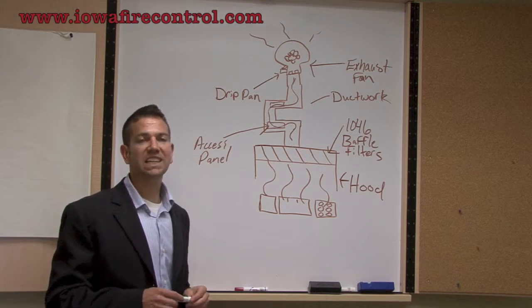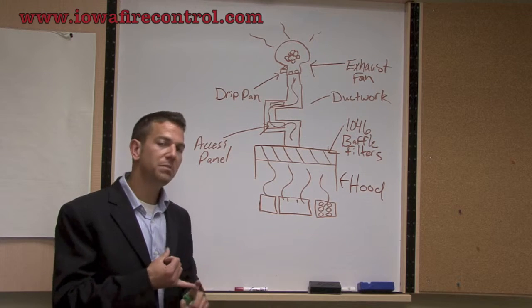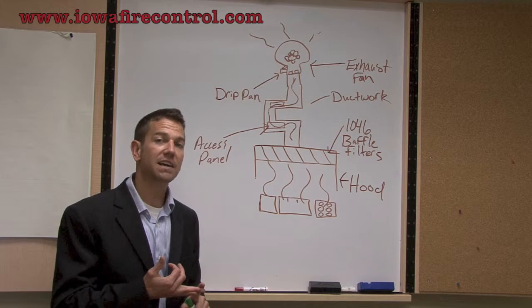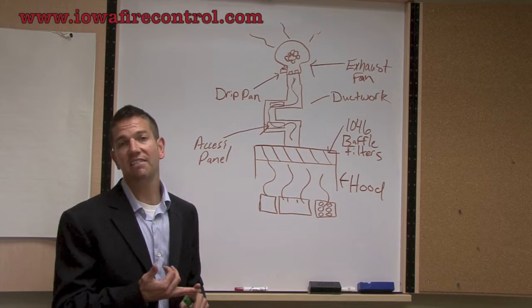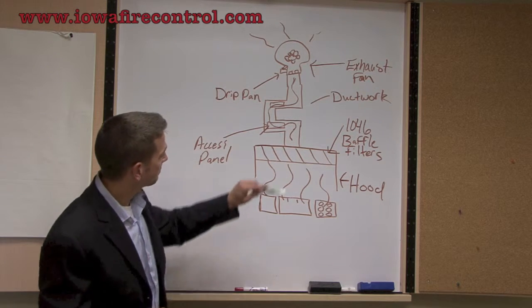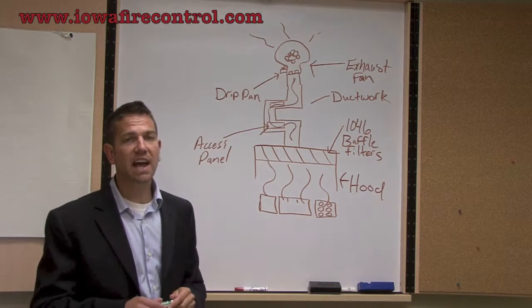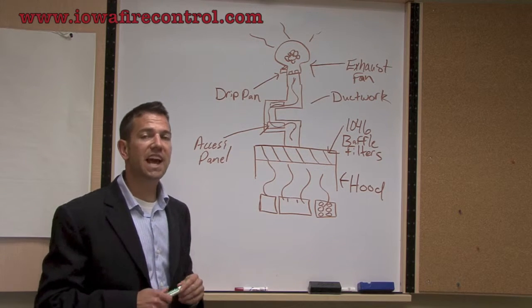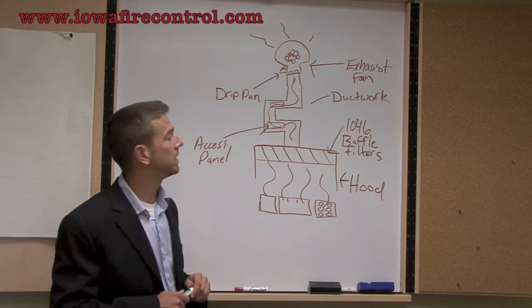When we go and clean a kitchen exhaust system, we need to be able to access it so we can inspect it, and also access it so that upon inspection, if it's found to be grease laden, we can have it cleaned. There will be strategically placed access panels within that system. If you're interested in access panels, check out our videos on our website.